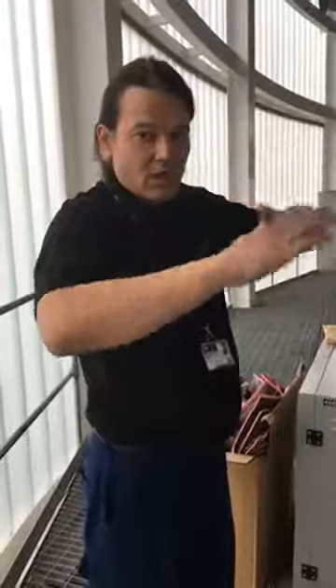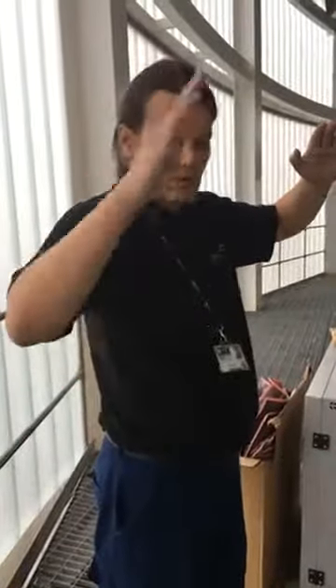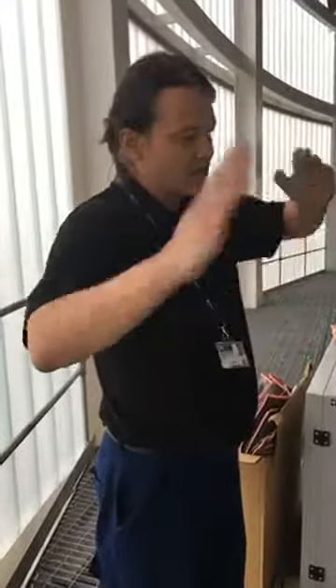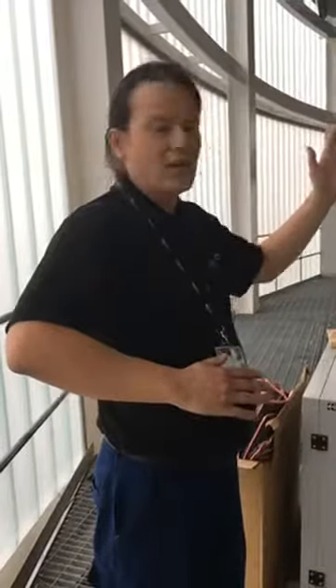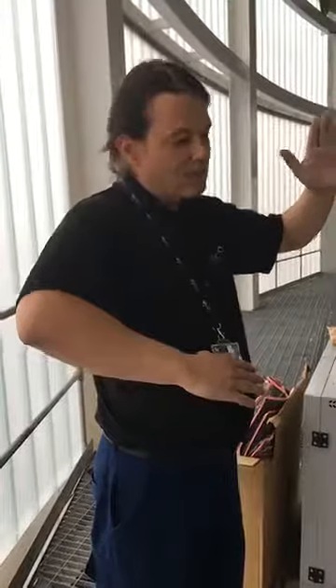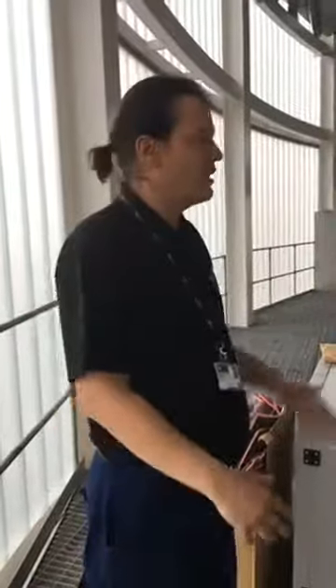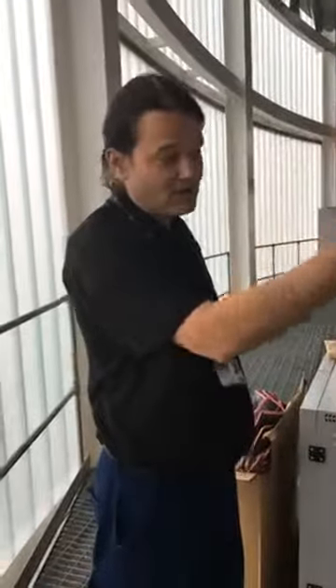Normally what happens is you have 2 valves and they rock in between. We've set the temperature at 21, so it gets to 23, the hot valve closes down, and as it closes, the cooling valve opens, so you get a lot more cold air going in. Once it gets to 21, they'll both close down. Another sensor in the auditorium will eventually pick up heat, and it keeps going through that rocker stage, cooling then hot water heating.